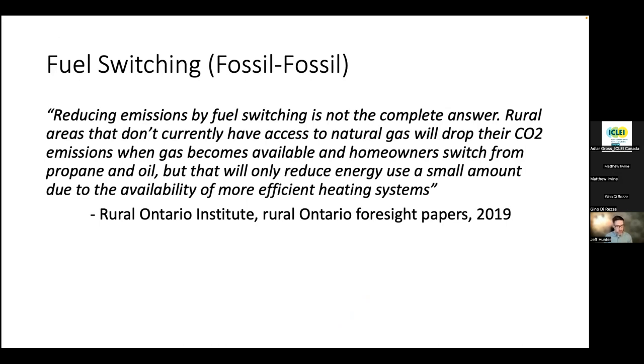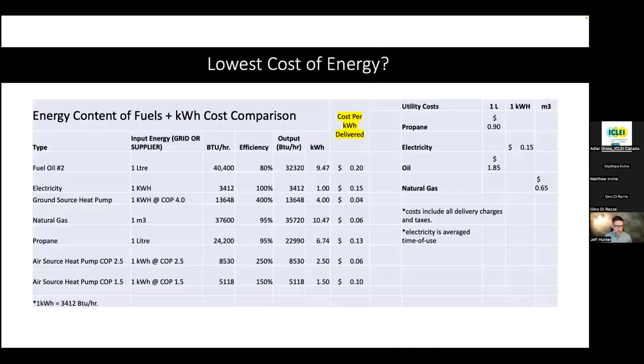Rural areas that don't currently have access to natural gas will drop their CO2 emissions when gas becomes available and homeowners switch from propane and oil, but that will only reduce energy use a small amount, due to the availability of more efficient heating systems. So you're going to get a bit of a net benefit because the fuel is presumably cleaner, though there may be an argument there with propane. But the energy use reduction is not coming down. And that's something that ground source heat pump systems, with their ground heat exchanger, can really benefit that equation. And we'll speak to that here, I think, on this slide.